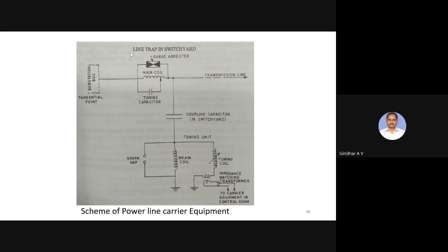Usually these line trap units, you can see, are between the bus bar and the coupling capacitor to the line. Usually we use this for remote measuring signals, remote control signals, as well as protection signals and telephone conversations. These line traps are used to prevent high frequency signals from going towards undesired directions. Mainly, if you could see here, a main coil is there, a tuning unit will be there, and an over voltage arrestor will be there.